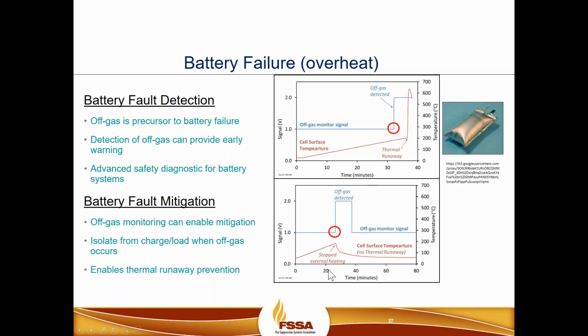In the graph on the bottom, you'll see that when off-gas is detected, we stop or eliminate the abuse factor from occurring, and this prevents thermal runaway from occurring. So here we used a battery management system to stop the overheating of the cell itself, and we prevented thermal runaway from occurring.